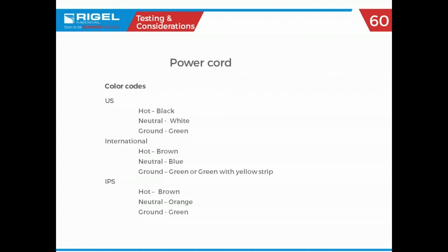Color codes, again, I'm going to go quick through some of this stuff. Everybody knows US black, white, green, international brown, blue, green, sometimes with a yellow stripe. IPS, isolated power sources: hot brown, neutral orange, ground green. Your ORs are almost always isolated power sources now because it's another safety consideration. That's where the patient is at the weakest moment. If you're going to do electrical safety testing, you cannot do it with an isolated power source because you're going to get bad readings.